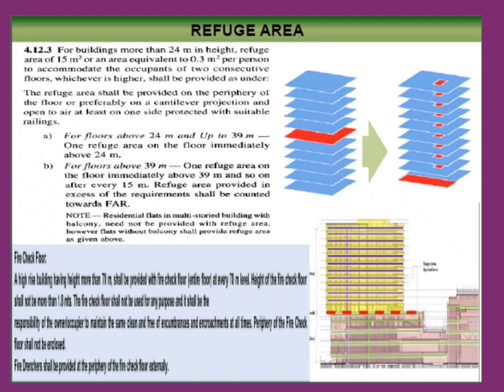Friends, we are discussing now refuge area. A refuge area is to be provided for fire evacuation purpose because all persons cannot rush to the ground floor. Persons have to be provided a refuge area every sixth floor for floors above 24 meters and up to 39 meter. One refuge area on the floor immediately above 24 meter has to be provided. For floors above 39 meter, one refuge area on the floor immediately above 39 meter and so on after every 15 meter.